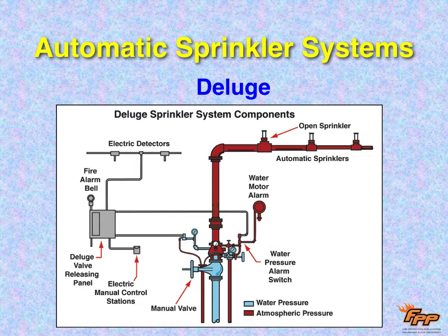Deluge systems are different than wet pipe and dry pipe in that they're only used for small portions of the building, usually over specific equipment. And in deluge systems, the pipe is dry and the sprinkler heads are open. So when the sprinkler system turns on, which I'll explain to you in a second how it happens, the water comes out of every sprinkler head. Now, these are not used in whole buildings. So unlike Bruce Willis movies and Die Hard and all of that kind of stuff, there isn't a system that exists where you set your cigarette lighter by a sprinkler head and it pops open and waters everywhere in the whole building.